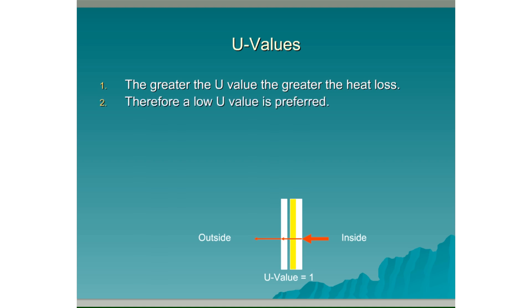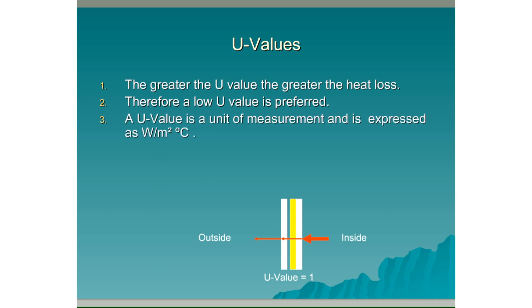Therefore a low U value is preferred. The greater the U value, the greater the heat loss; the lower the U value, the lower the heat loss. A U value is expressed as watts per meter squared degree Celsius.